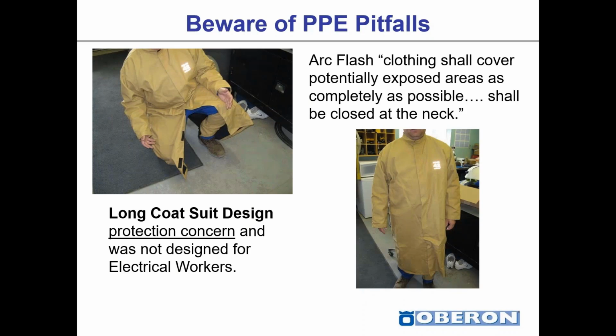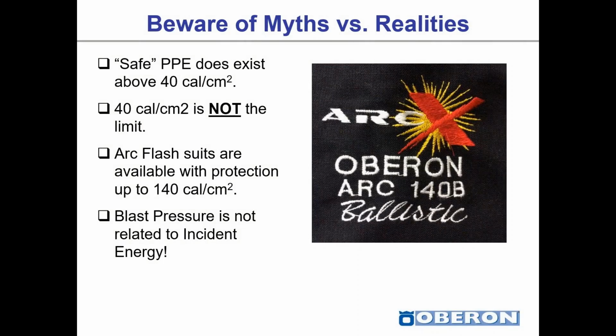Beware of PPE pitfalls. A long coat suit design is often a pitfall in industry. If a worker were to squat, just like my image on the screen here with a worker with their knee on the floor, you can actually see the blue part of their coveralls, and that is a gap. So if a worker were involved in an arc flash, they could sustain some rather significant burn injuries in that exposed area. This type of system is rather difficult for a worker to use because they have to keep their knees together when they squat. So we want to use, in my opinion anyways, a bib overall or a pant with the coat and have sufficient overlap. So we have lots of protection for the worker in the event of arc flash exposure.